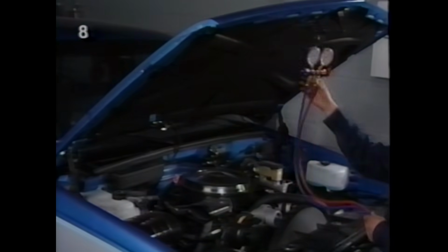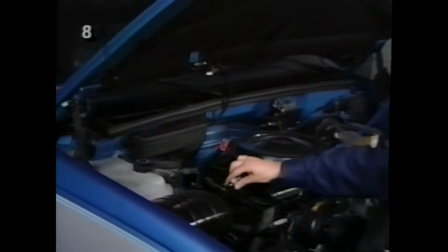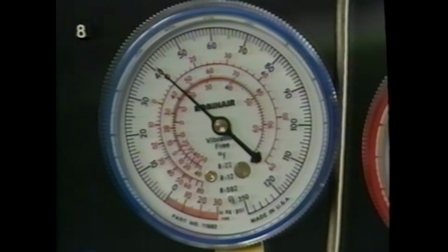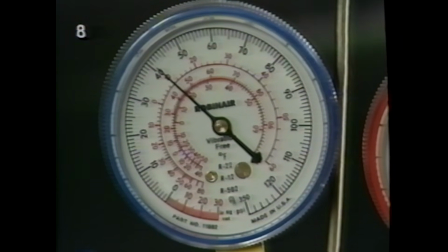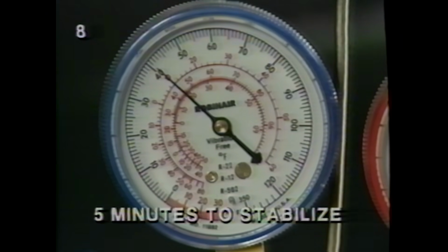Now, let's go through a quick review of the performance test. Connect the refrigerant gauge set with the low pressure gauge hose at the accumulator service port and the high pressure gauge hose to the service port in the compressor discharge line. Run the engine at the specified RPM found in the appropriate service manuals. Set the controls for maximum cooling for 5 minutes or long enough to stabilize the air conditioning system.